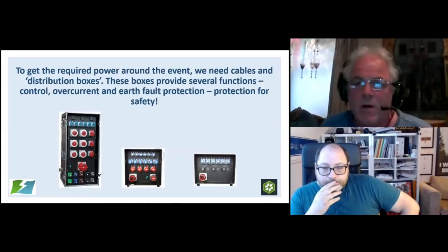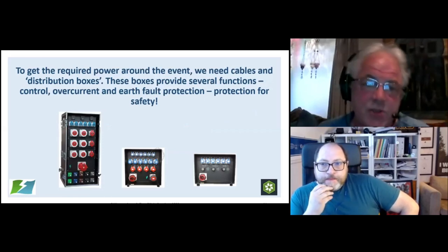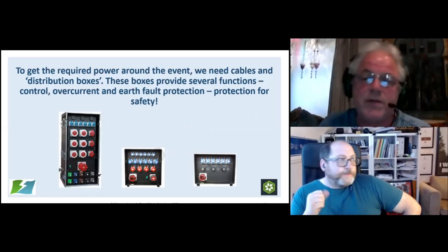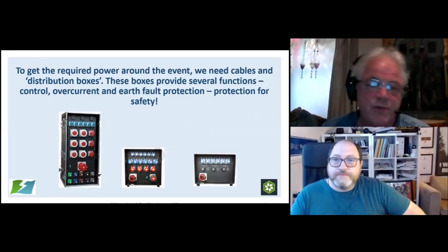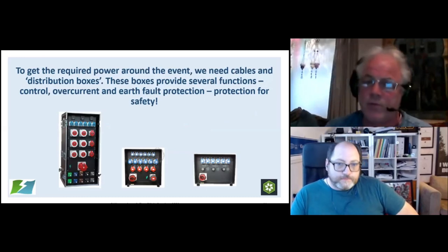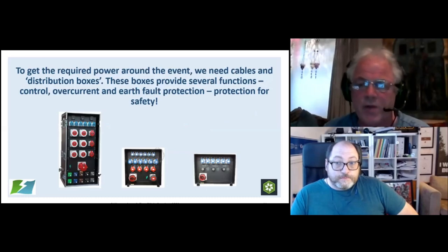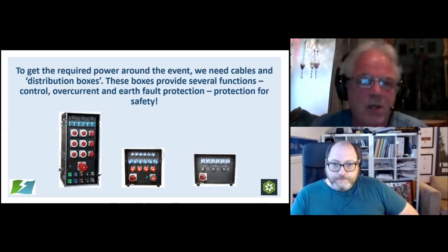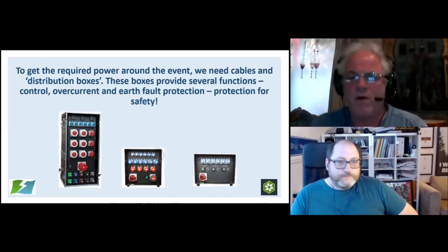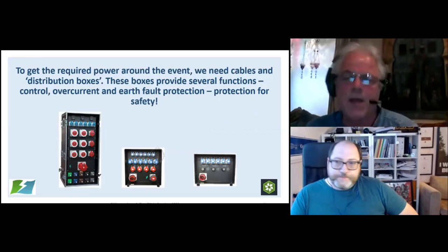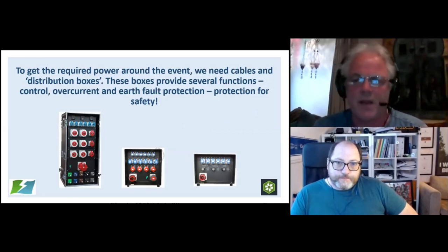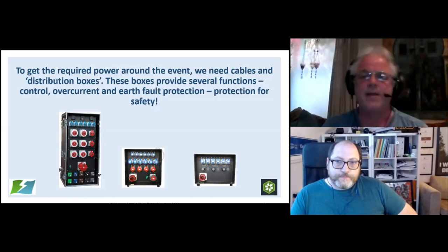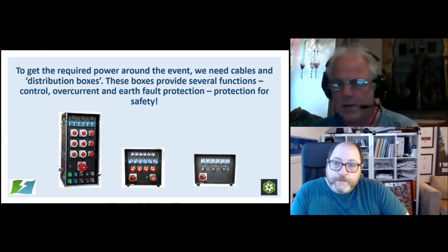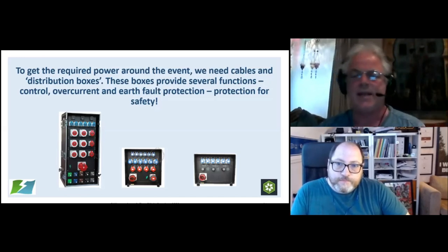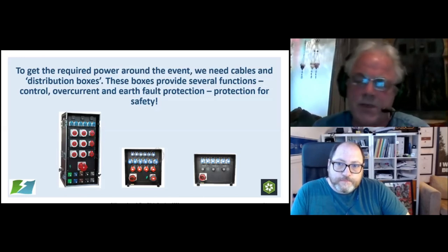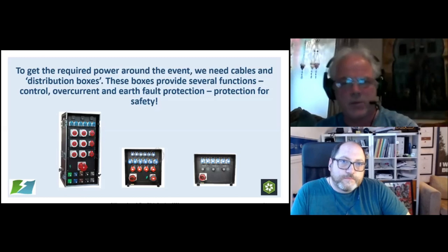To get the required power around the event, we obviously need cables and distribution boxes, and they come in all sorts of shapes and sizes. They provide several functions. You've got control, overcurrent protection, earth fault protection, and you can have monitoring, metering and all sorts of stuff in there, depending on your specification for your distribution. And these should arrive on site all inspected, all tested, all ready to go. And this is the great thing about installing temporary systems to 7909. The equipment arrives on site pre-tested, pre-inspected, all signed off. We haven't got to do any dead testing. It's just a case of putting it together, building it to the design, and once we've got it all built, it can be switched on and we can then test it.